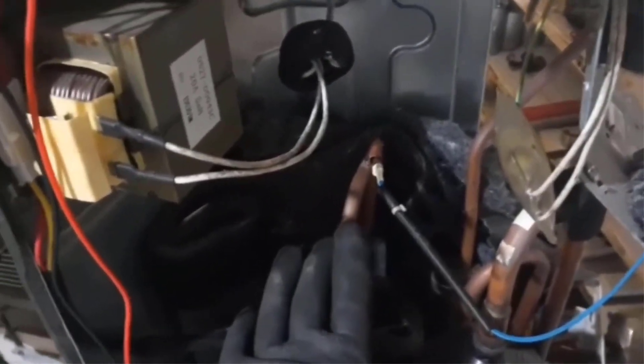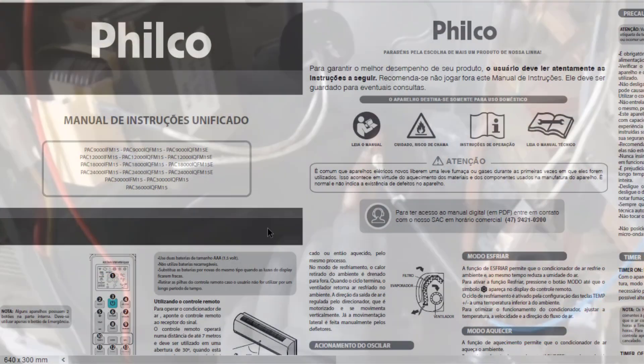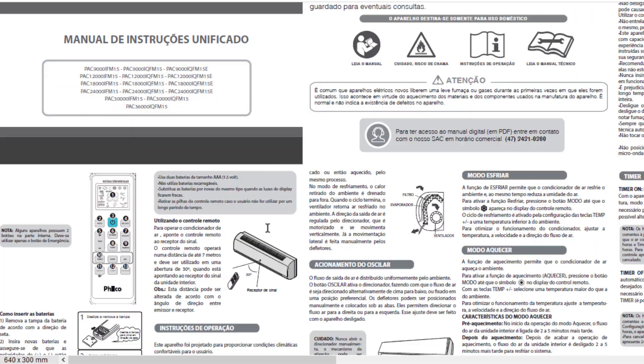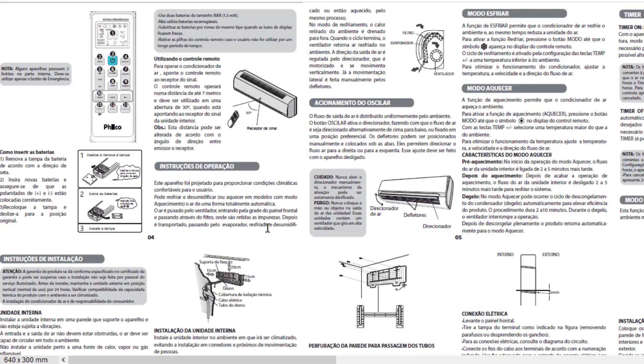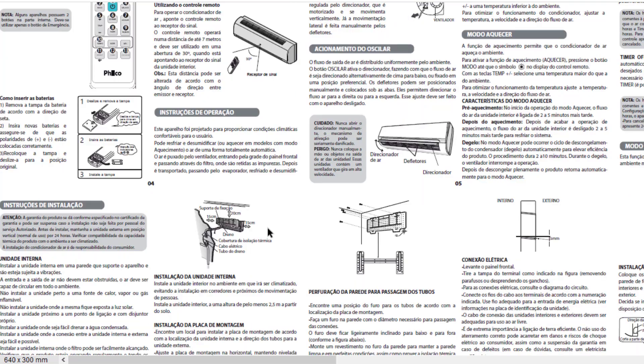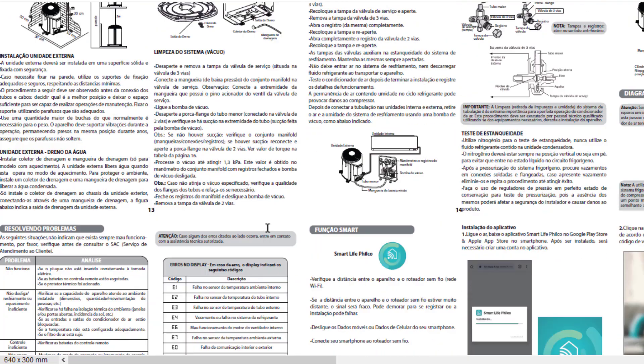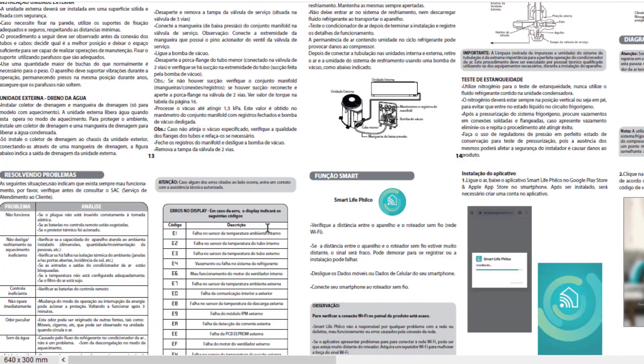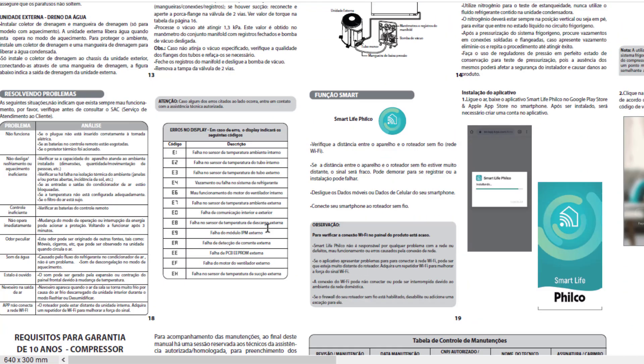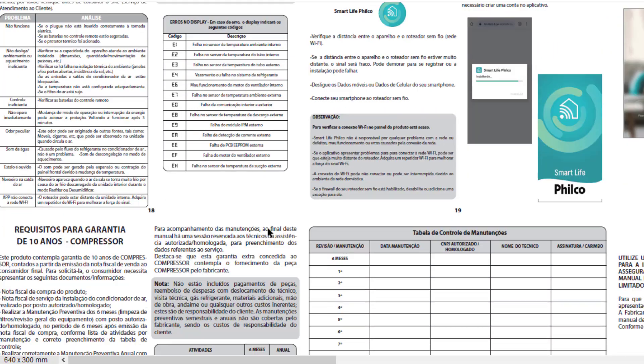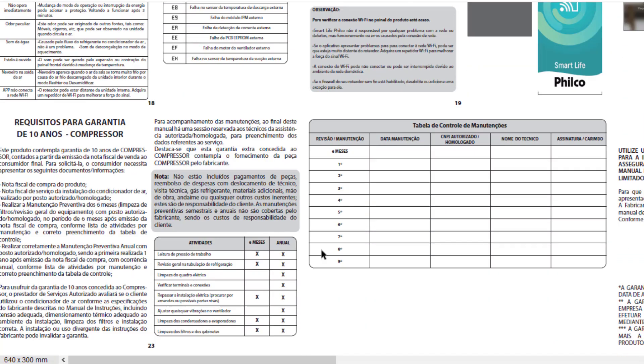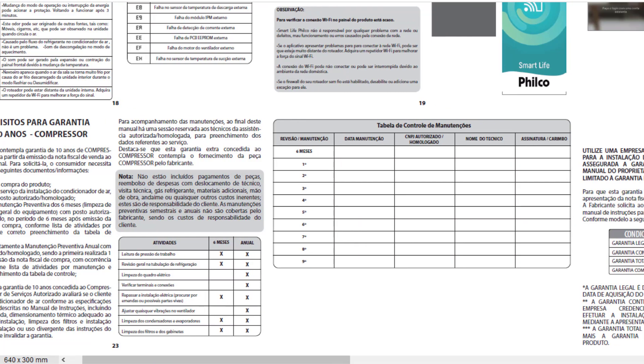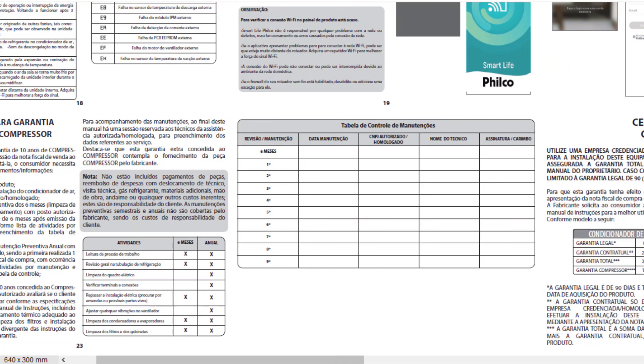Remember that every time you open a piece of equipment, you need to have the electrical manual and know exactly which temperature sensors are in the equipment and which of them are NTC and PTC. To perform the diagnosis and maintenance correctly, you need to know which sensors are in the equipment according to the manual you are reading, which can vary from one brand to another.